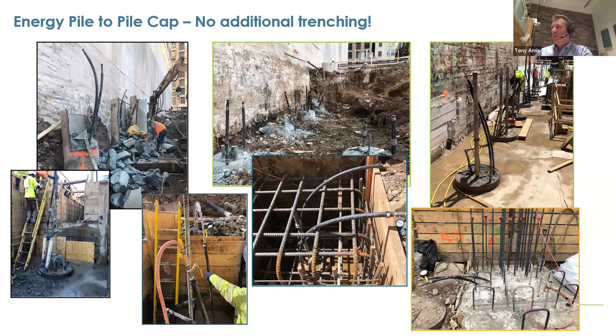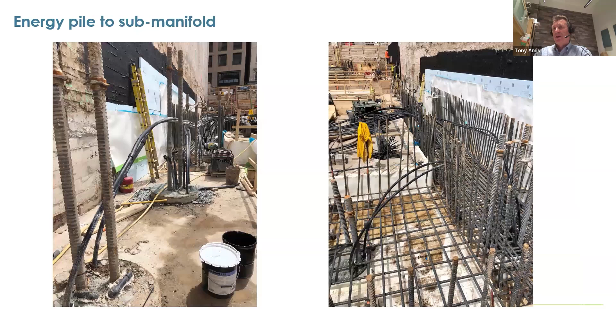What you see on the bottom right is the pile cap constructed with the loops left under pressure, just to verify. When we come back to make the next connection, the first thing we look at is that the pressure has been maintained, so we can start to run all the geothermal loops back to what we'd call a submanifold. The circle here shows the location where two submanifolds will be sited.